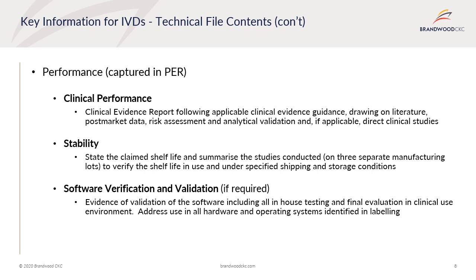The next one, very important with IVDs, and that's stability. Because IVDs are going to have reagents and have components to them that may have different manufacturers, may have different manufacturing processes, so on and so forth, you need to be able to show that the stability of the product will be maintained for the life of the product. And so that if you have something happen, whether it's the temperatures rise or that the transportation goes in a non-pressurized aircraft, that you have a study to prove that the result from your device or your IVD will be the same.